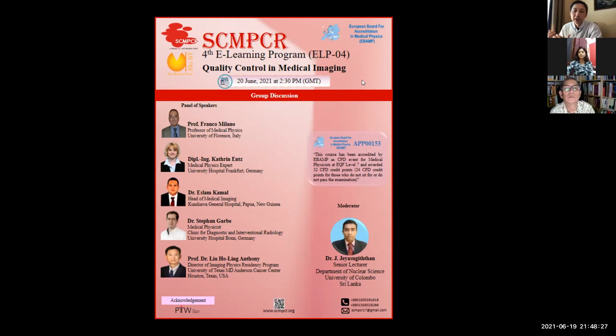What we need to pay more attention to is the ACR phantom testing. For ACR phantom testing, the most important thing is making sure it's in the center of the coil, and also the level is very important. We need to have a level to make sure it's level in all three directions. By the way, buying a good level that's MRI safe is also important, but that's usually cheap. It can be bought in many places. The plastic level is important.